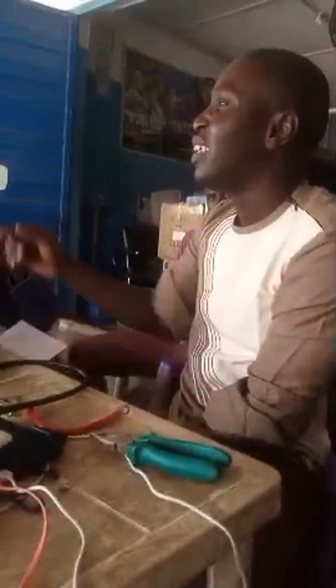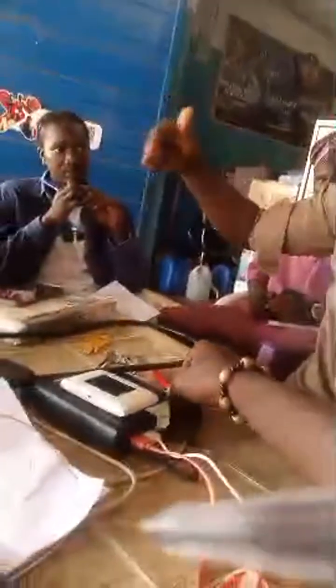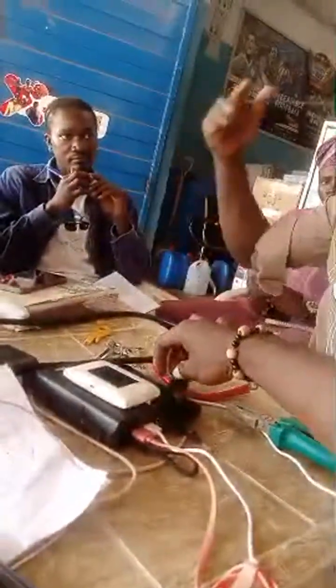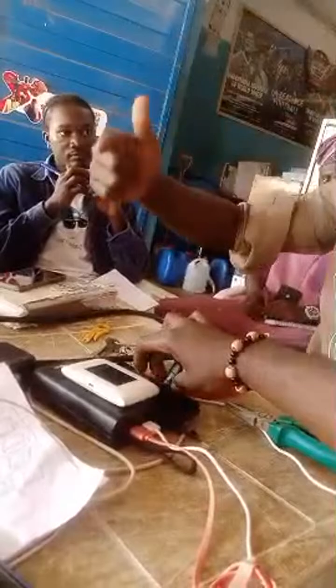So I'm saying this one on the perfect level, but on the reality level, when you get to site, you need to know the voltage that is running on that side. That voltage is what you use to divide the capacity of the inverter. So let's say it's 180 volts coming from NEPA there. You say 2.5 kVA divided by 180, it will give you the amps that will flow. Is that the amps you carry to the chart and check on the cable gauge?